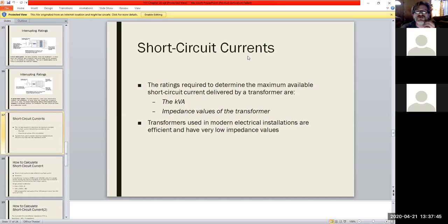And that's how you have to look at that. And generally for that, you'll notice they have a rating there, the kVA. Now, k is the thousands, and VA is, of course, instead of using watts, we use VA, volt-amps, the ampacity for the overall circuit. And then we'd look at the impedance values of the transformer itself and what's involved there.